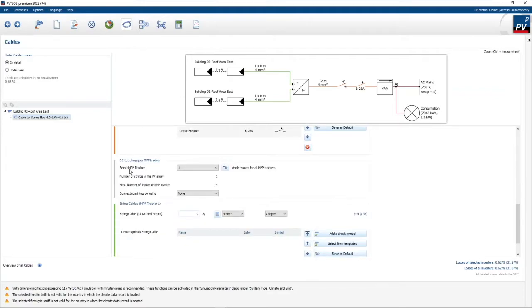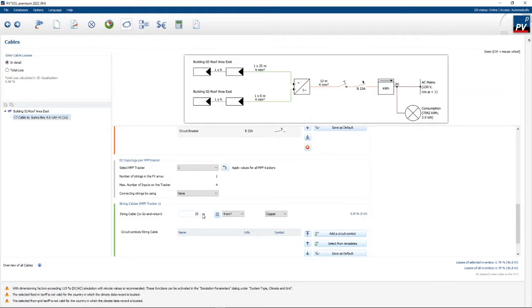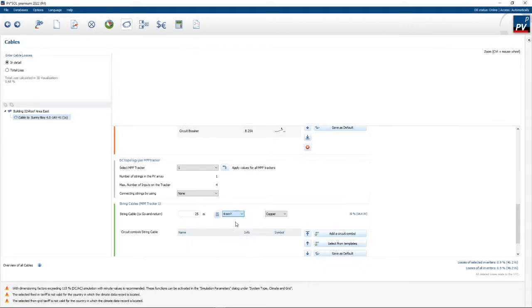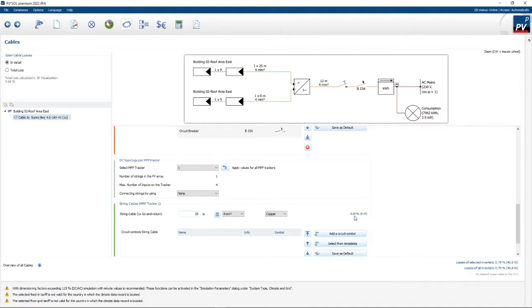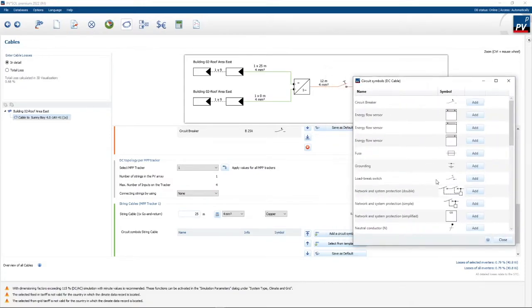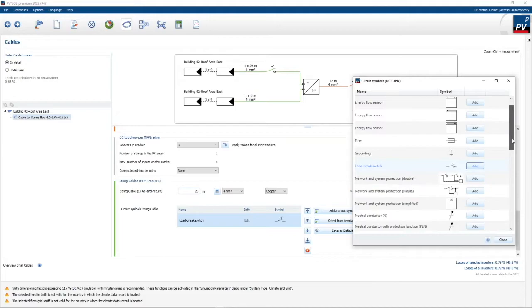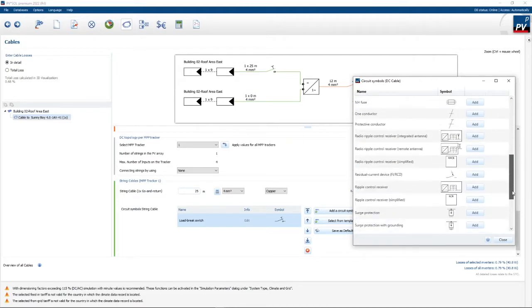On the DC side under MPP tracker one, I want to specify the string cable length from the modules to the inverter and back — let's say 25 meters. If you click the little calculator, it tells me I need a 2.5mm² cable. You can also override it to a bigger size. To the right it will tell you the loss in your cable — 0.35% loss, which is not too bad. I also want to add an isolator into my string and some surge protection.